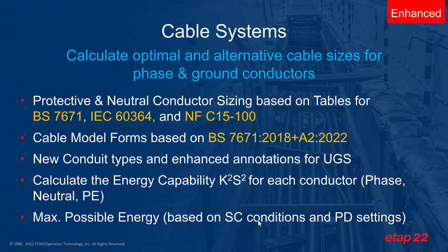You can also calculate the energy capability within the cable editor, which is the K square S square for each phase, neutral, and protective earth conductor. And you can also compute the maximum possible energy based on the short circuit conditions and the protective device settings within the same cable editor as well.